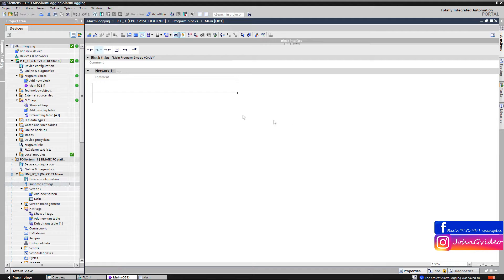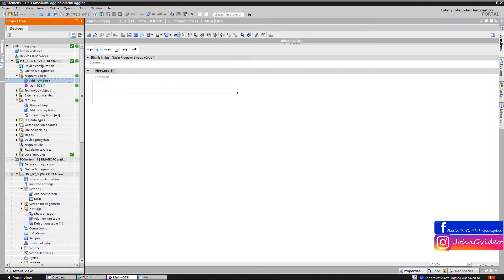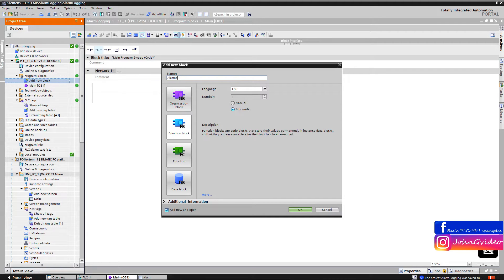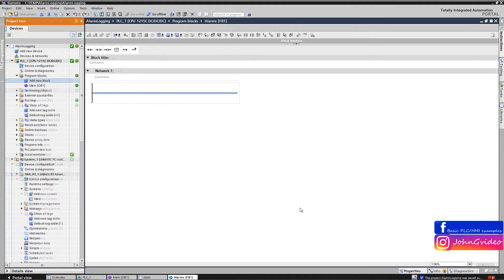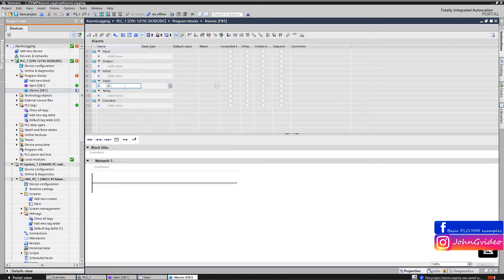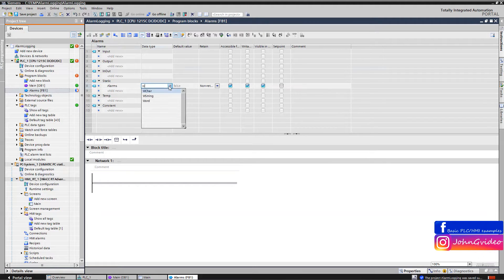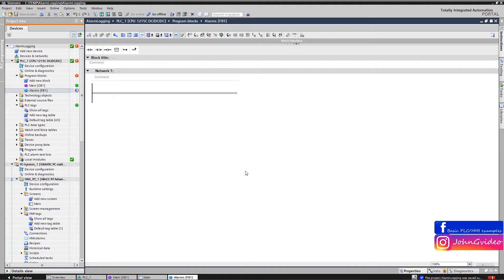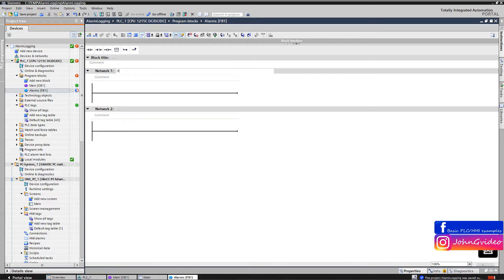We use the PLC 1215 and the HMI Runtime application. First, we create a function block with the name 'alarms'. In this function block we define the static variable 'alarms' of the data type Word. We save the project and in this function block we create two networks. In the first network we activate alarm number 1, and in the second network we activate alarm number 2.